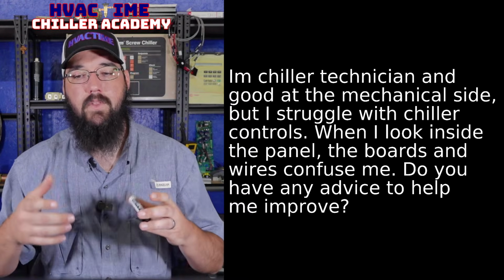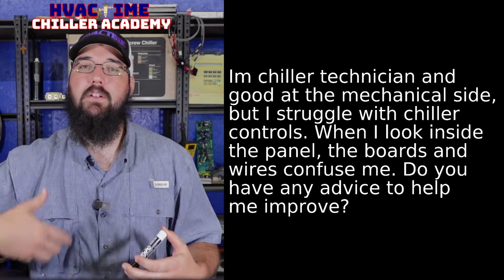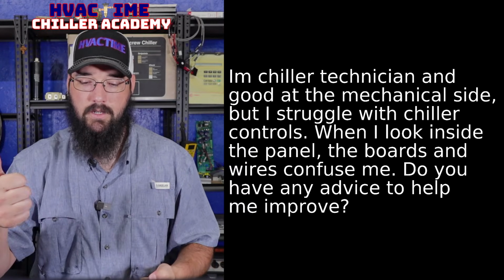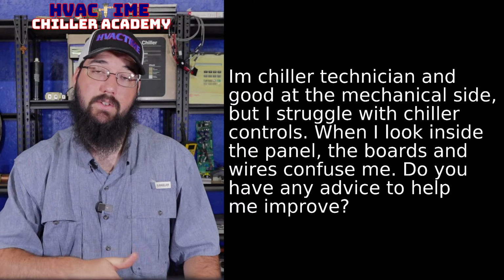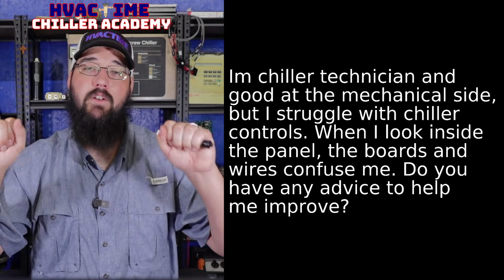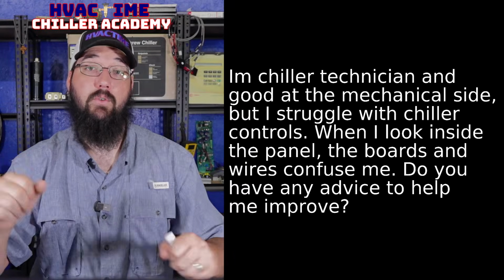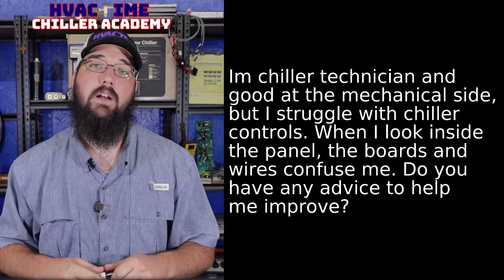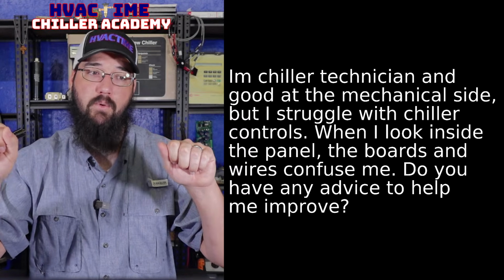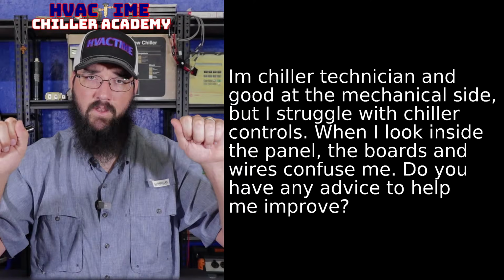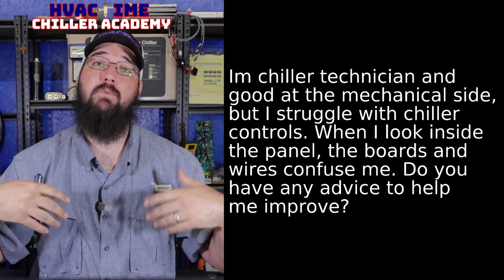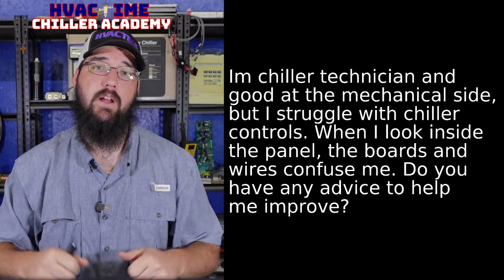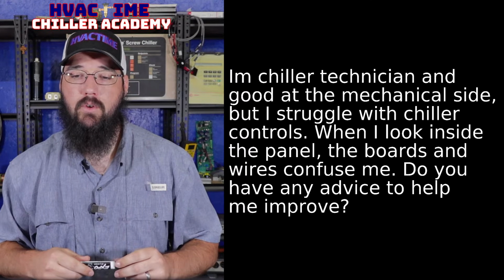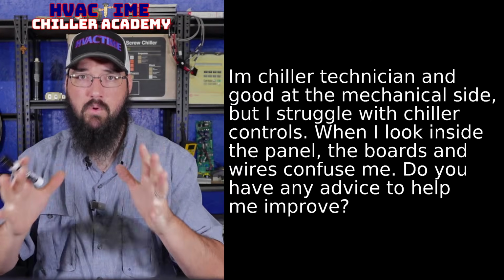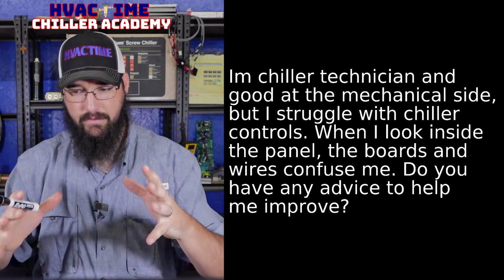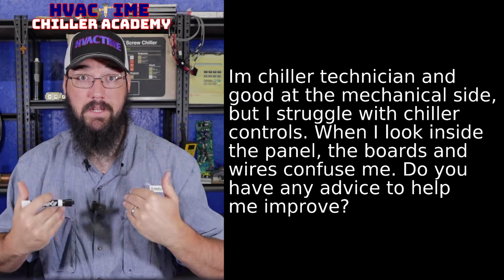So those are just little things we have to take into account that can make a successful or unsuccessful troubleshoot. If you have an ungrounded circuit but you're testing all your points to ground, you're going to get a bunch of crazy voltages. Versus if you're testing from, say, point to common, then you'll get proper voltage, but you'll get what we would call a ghost voltage if you test that to ground. So yeah, there's more to tell, but for me, it starts at the schematic.